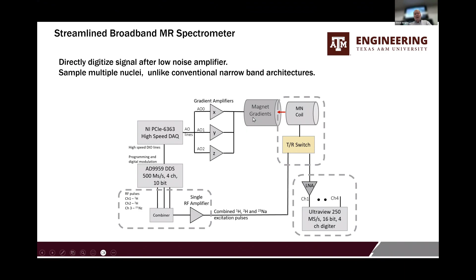Here's simultaneous, truly simultaneous. So this one RF pulse excites both proton and deuterium, and then the echo comes back from both. And this is a phantom with decreasing concentrations of one and increasing of the other. And that's what we get. Obviously, the resolution for 2H is lower.